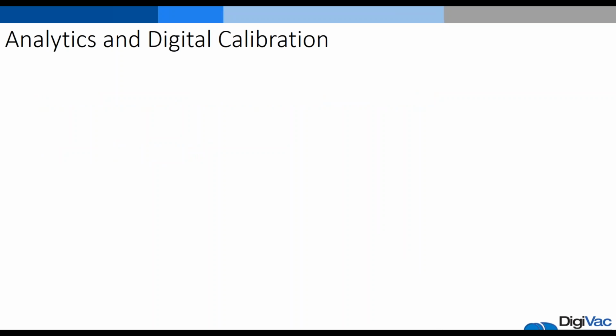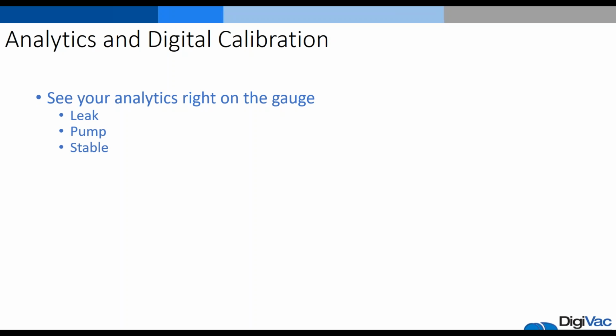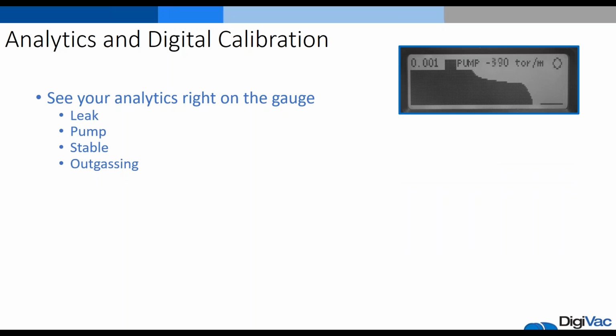So to move forward, analytics and the digital calibration of the gauge. You can see your vacuum analytics right on the gauge itself. You can switch between the settings and look at the analytics of the gauge. You can view it in graph form. You can see a leak pump. You can see if the pressure is stable, or you can see if it's outgassing. The image to the right is a vacuum pump graph, and you can see where the pressure is and where it's dropping, the torr per minute.